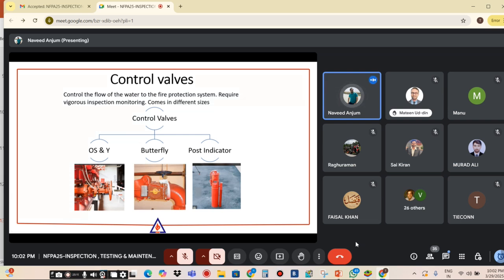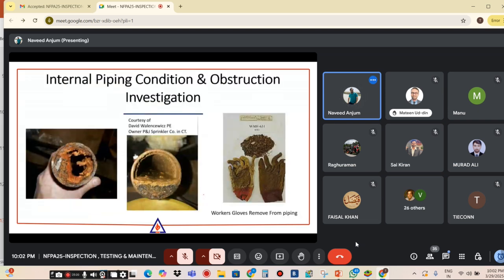OS&Y valves, butterfly valves, and post indicator valves, all types of valves you have to verify and test as per the given intervals. You can see the internal piping condition and obstructions. You can use different sound meters, pulse meters, for the piping condition and obstruction investigation by using a pulse echometer. You can use it to check the piping condition. Otherwise, this can happen with your system also.